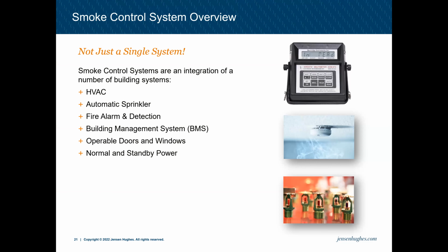This gets a little difficult, and not to reiterate this too much, but smoke control is not just a single system. It's an integration of a number of building systems, possibly including HVAC, sprinkler, fire alarm, BMS, operable doors and windows, power, etc. So, some of these systems might not be in the purview of an architect, but it's good to know an overview of what these systems are, and that you might be doing some work that might be impacting a system, then making sure the mechanical engineer of record or electrical engineer of record, or even the fire alarm programmer is aware of what these systems are, so they can incorporate them into the work that they might be doing.